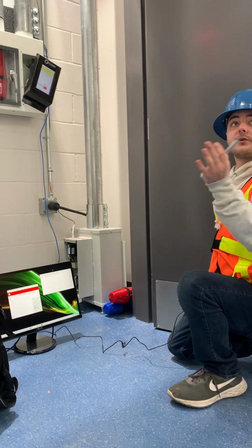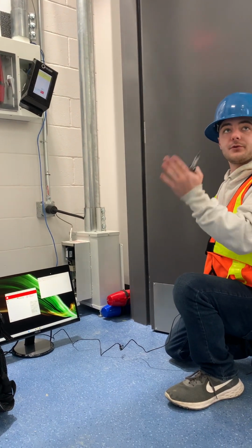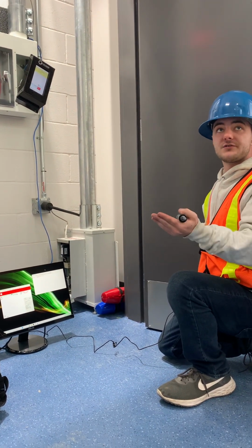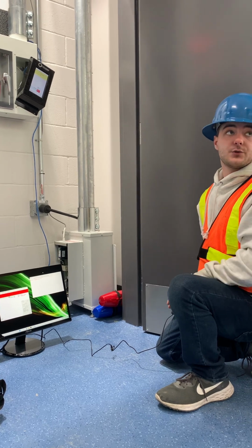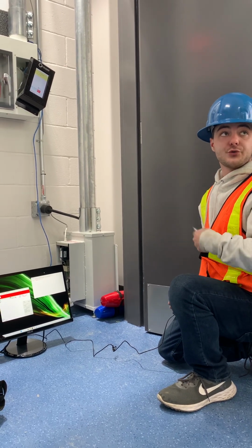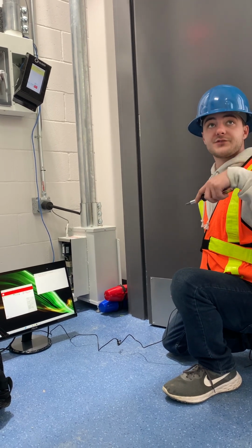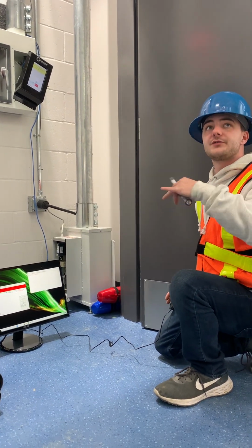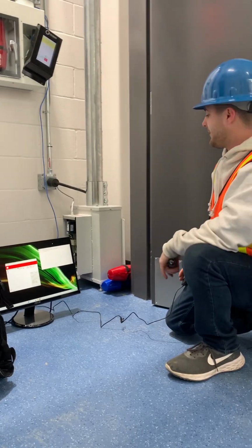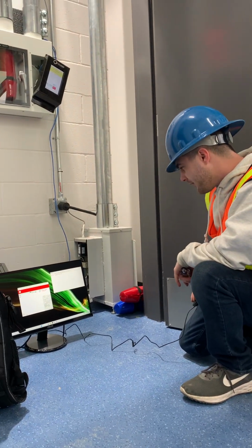Or a blower motor could be bad and that carrier could just be moving really, really slow, and there's a timer. So if they don't make it to the station in a period of time, it's going to be like, hey, this carrier's late, there's another issue. So it could be a lack of pressure or vacuum, or there could be a leak of air in that diverter, for example. There's a very slim chance of that happening, but I've definitely had that happen.